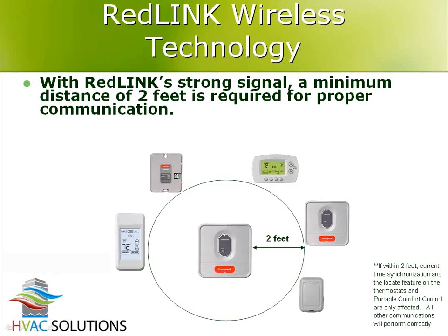There are some rules associated with these things. One of the biggest rules is you can't have things too close to one another. So the minimum between most devices is 2 feet. That's not a problem for most things. Having the thermostat 2 feet away from the furnace is not an issue. In fact, that's probably the reason you chose wireless to begin with, because you had a long distance between the two. But maybe you have 2 pieces of equipment that are right next to each other, 2 furnaces, for example, and you want them to both have wireless.